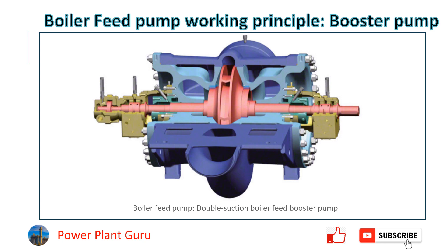The booster pump takes suction from the deaerator and discharges high pressure water to the boiler feed pump suction. This is a double suction type booster pump where water comes in from two sides, passes through the impellers, and high pressure water comes out from the discharge casing. There may be single suction types as well depending on the requirement. This pump's discharge pressure feeds into the boiler feed pump suction.